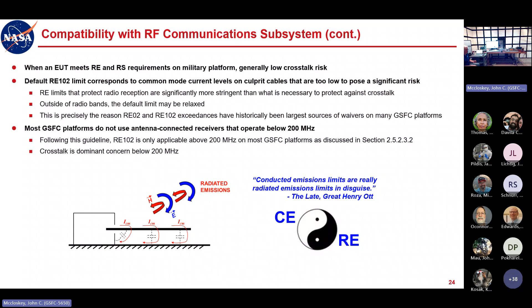So looking at the RE102 test method here, we have specific antenna types in each frequency range. And one thing that's non-negotiable is that if you're saying you're doing RE102 per the mil standard, then that means the antenna is placed 1 meter from the setup boundary. I'll have more about this in the RE102 session, but the antennas are calibrated at that distance for a reason. Just a quick overview: you have an antenna that's this big, this far away from a test article. Are you in the far field? Exactly, probably not.